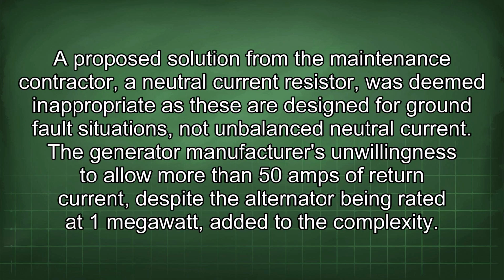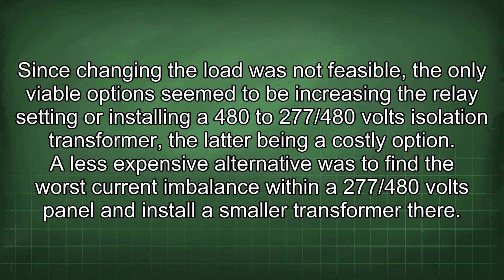A proposed solution from the maintenance contractor, a neutral current resistor, was deemed inappropriate, as these are designed for ground fault situations, not unbalanced neutral current. The generator manufacturer's unwillingness to allow more than 50 amps of return current, despite the alternator being rated at 1 megawatt, added to the complexity. Since changing the load was not feasible, the only viable option seemed to be increasing the relay setting or installing a 480 to 277/480 volt isolation transformer, the latter being a costly option.